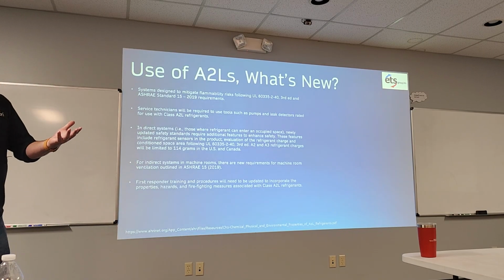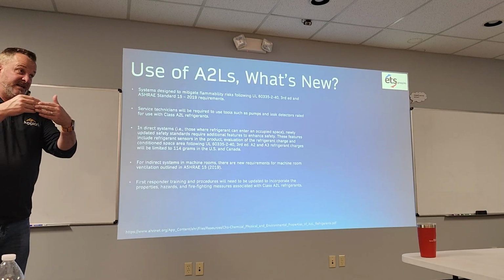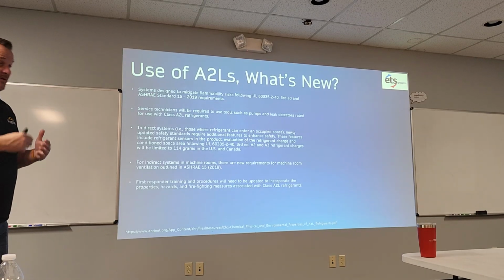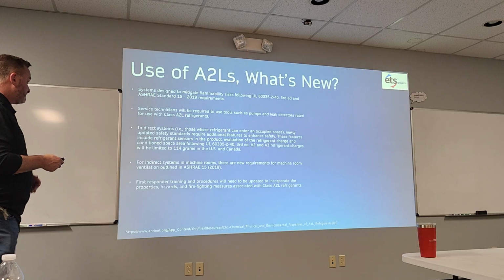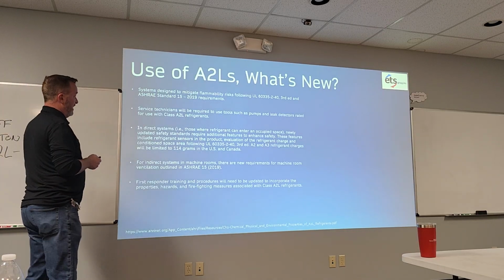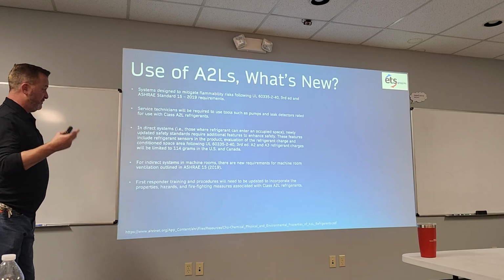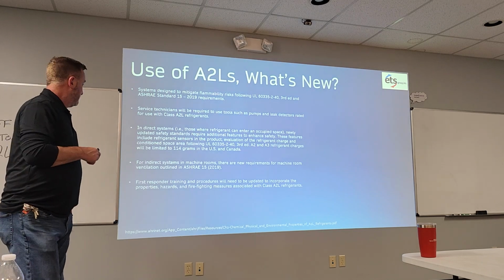If it's a 454B system, the leak detection system will be testing for 454B, or for 32. Service technicians will be required to use tools such as pumps and leak detectors rated for A2L refrigerants. I'll go over that as well.